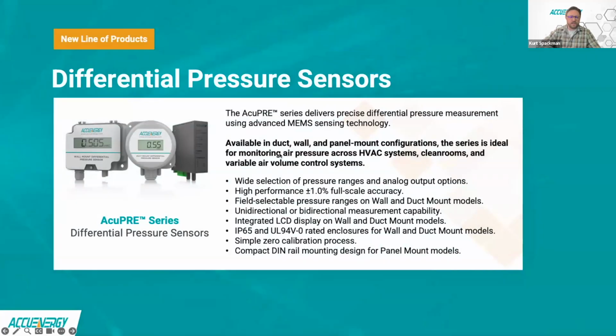Again, just to address some of the high level specifications, the three configurations are the wall mount, which is the one on the left. That is going to be our most universally mountable configuration. The duct mount in the middle there, and then the panel mount unit, which is 35 millimeter DIN rail mount. These products are meant for monitoring differential pressure in non-caustic, non-corrosive air. So, monitoring static pressure within ductwork, monitoring pressure in stairwells and buildings, and so forth.